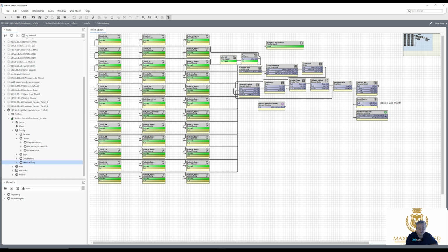Bit of logic in there for resetting a router. I must have had issues with the router, and they've written a little bit of logic there. Yeah, they've used analog output 1 on the NDIO to reset it. So you would have used a 10-volt relay, I would have thought. What a waste of an NDIO just for that.